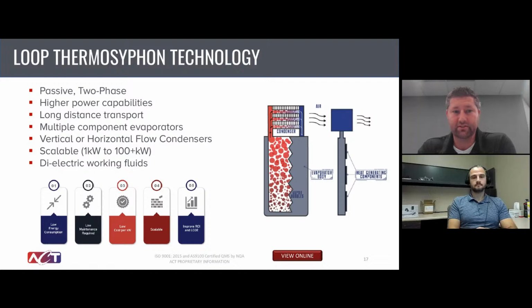A thermosyphon can be very similar to a heat pipe, just unwicked, and knowing that you need to couple your heat sink above your heat source. So if you have that scenario, you can use thermosyphon technology and get the benefit of the gravity assist. What ACT developed and is implementing in the field is loop thermosyphon technology, which takes it to a higher or more advanced level and enhances your heat transport capabilities even further.